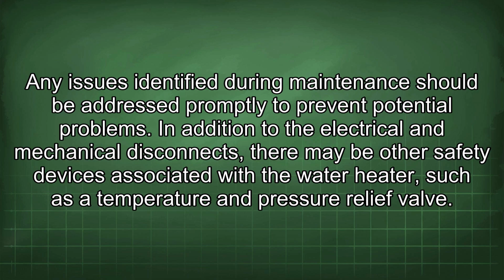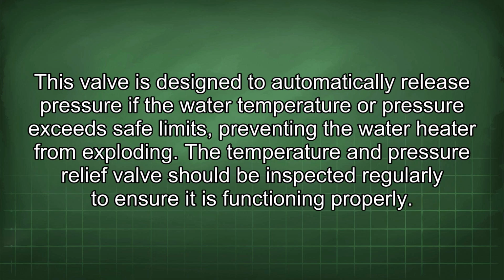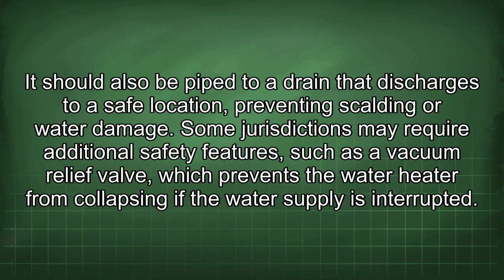In addition to the electrical and mechanical disconnects, there may be other safety devices associated with the water heater, such as a temperature and pressure relief valve. This valve is designed to automatically release pressure if the water temperature or pressure exceeds safe limits, preventing the water heater from exploding. The temperature and pressure relief valve should be inspected regularly to ensure it is functioning properly. It should also be piped to a drain that discharges to a safe location, preventing scalding or water damage.